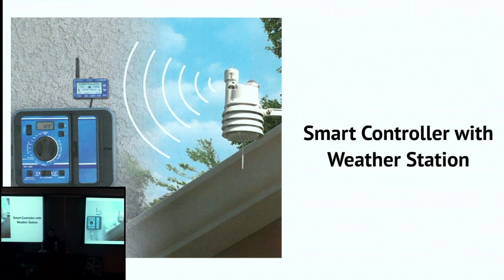Okay, so the other thing about controllers is get with the manufacturer of whatever controller you specify, and learn how to program the controller. So when you are checking this controller with the contractor, you can also check his programming and make sure it's what should be programmed into the station based on your water calcs. And Janet will talk about water calcs a little bit later.